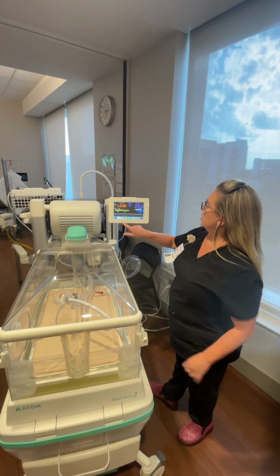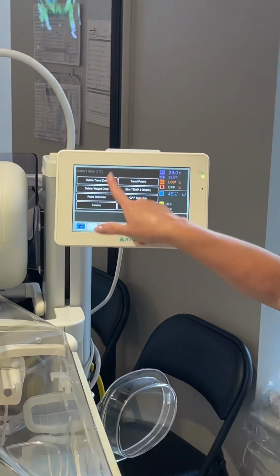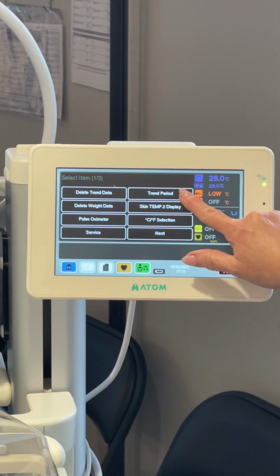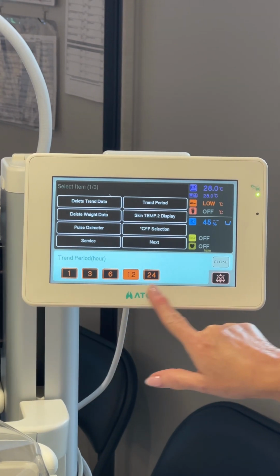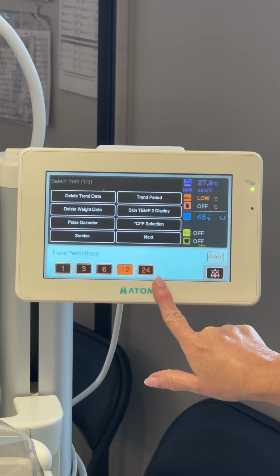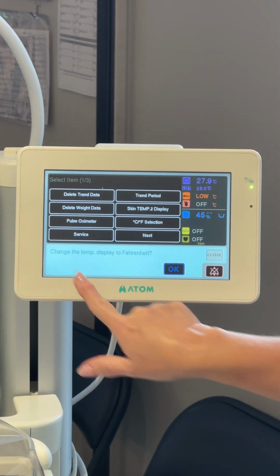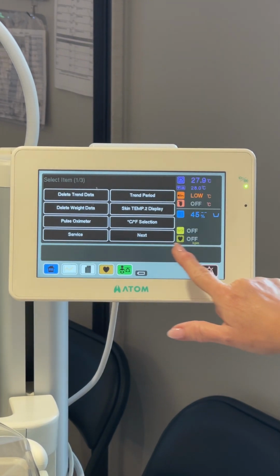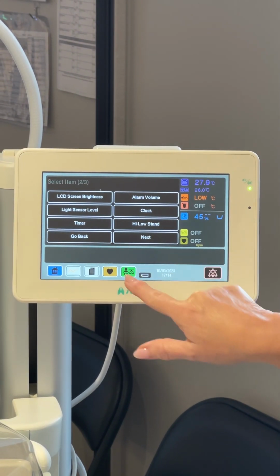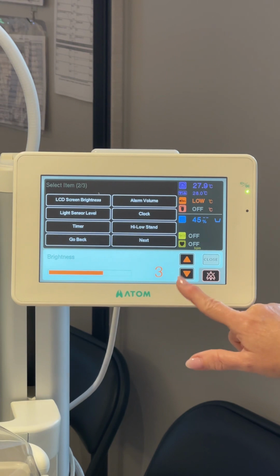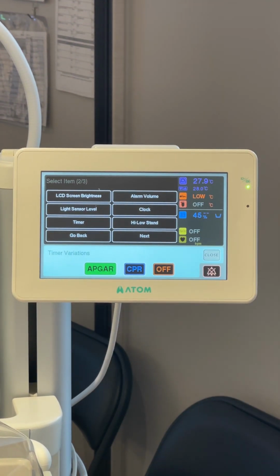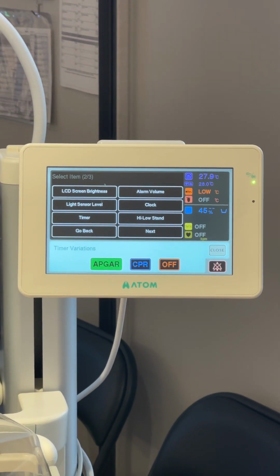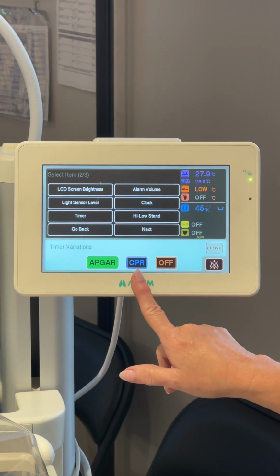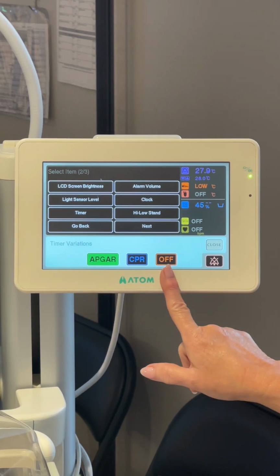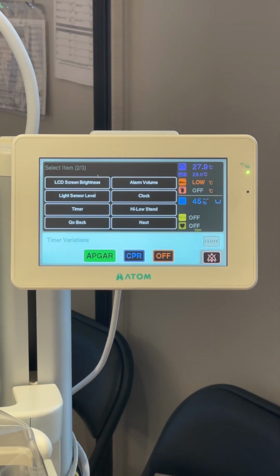Let's revisit that drop-down menu again just for the final few things. Service screen is for biomed. So if you're trending and you'd like to change your trending period of time, you can. There's a Fahrenheit to Celsius button that's very easy to change back and forth. You can change things like the brightness of the screen. There are 2 timers. When this is opened up into warmer mode, you have an APGAR timer as well as a CPR timer, or by pushing off, it'll go off the screen altogether.